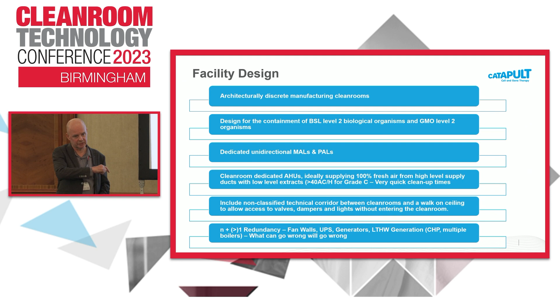Clean rooms ideally need dedicated air handlers. So the best way to organise this, although it's quite an expensive way of organising it, is to have the air handlers running on a full fresh air with no top-up or recirc. So single pass, in and out, no sharing across clean rooms. As I mentioned, it's always prudent to include a non-classified space between the clean room environments to really reinforce that physical architectural segregation. And we've also found that redundancy is really important, particularly when the utilities and services that are operating are integral to our containment and cross-contamination avoidance policy.